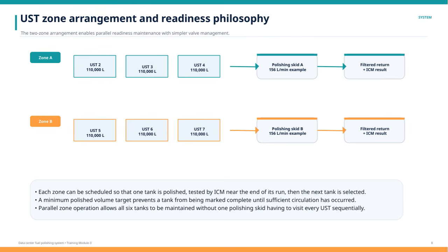In each zone, there is a dedicated polishing skid operating at around 156 liters per minute, which circulates and polishes the fuel in the tanks. After polishing, the fuel is filtered and then tested using the inline condition monitor, or ICM, to ensure quality. The key point is that each zone can be scheduled independently. For example, one tank gets polished and checked near the end of its cycle, while the next tank is prepared for polishing. This scheduling ensures continuous fuel readiness without disrupting the entire system.